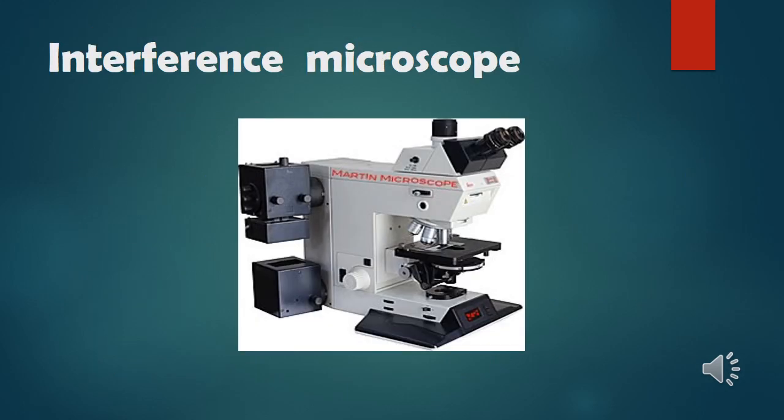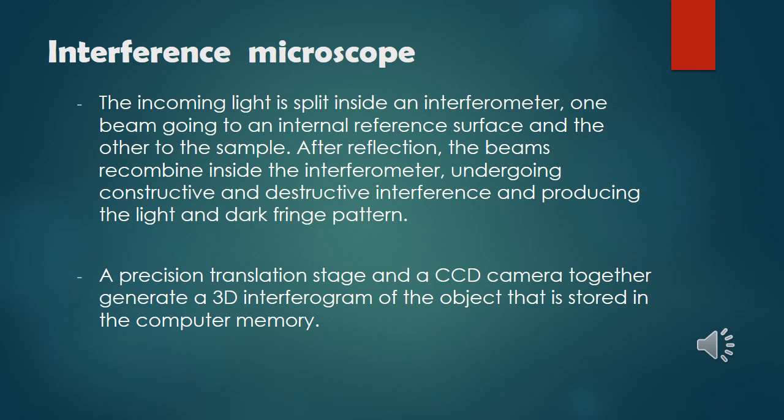Lastly, we have the Interference Microscope. The main function of the Interference Microscope is that the incoming light is split inside an interferometer — one beam going to an internal reference surface and the other to the sample. After reflection, the beams recombine inside the interferometer, undergoing constructive and destructive interference and producing a light and dark fringe pattern. A precision translation stage and a CCD camera together generate a 3D interferogram of the object that is stored in the computer memory.